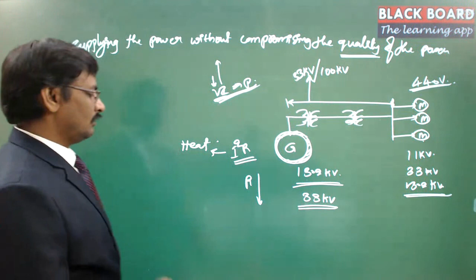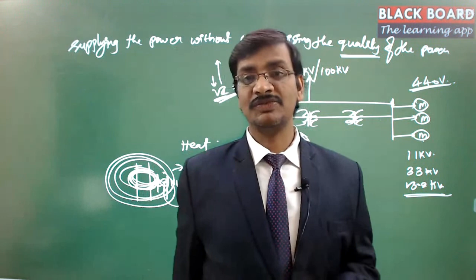On top of that, we will keep an insulation. On top of that, we'll keep one more winding here. This winding will have 110 kV. Then the insulation capacity that is needed in between is 110 kV minus 33 kV. Whatever the voltage value that comes out, for that you need to design the insulation capacity. That means you have got the advantage of avoiding the insulation for 33 kV. Because of this, the transformer design gives an advantage to raise the voltage to a higher value at a lesser cost. So the cost is reduced for the insulation.